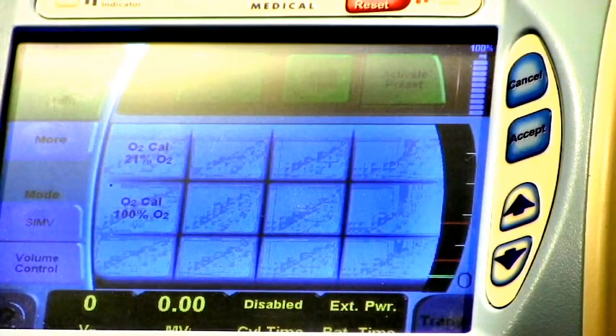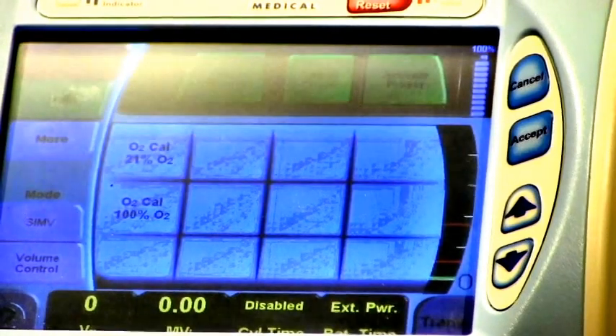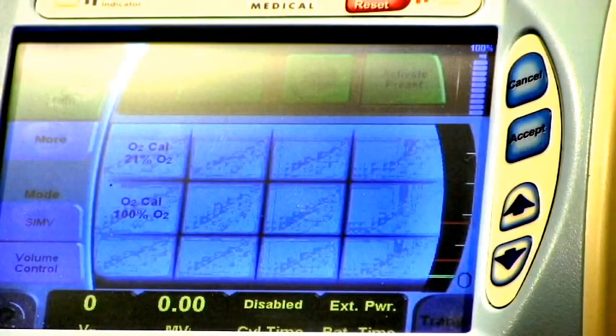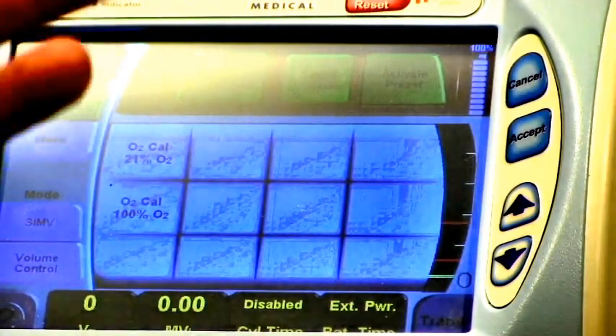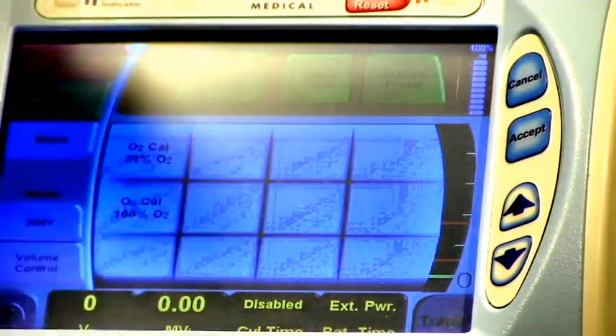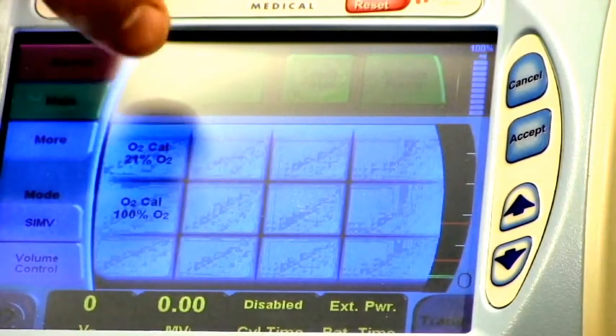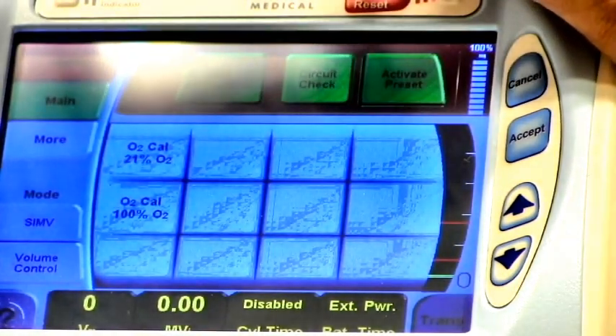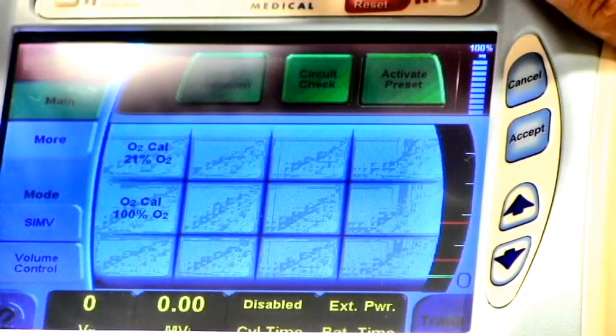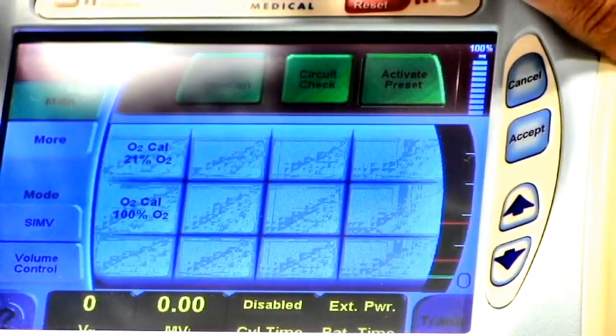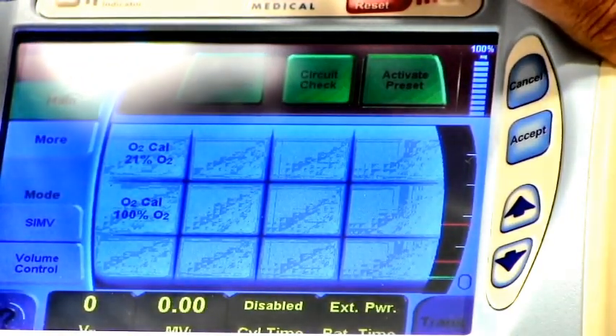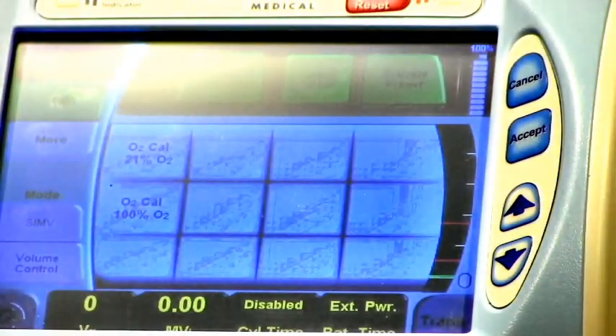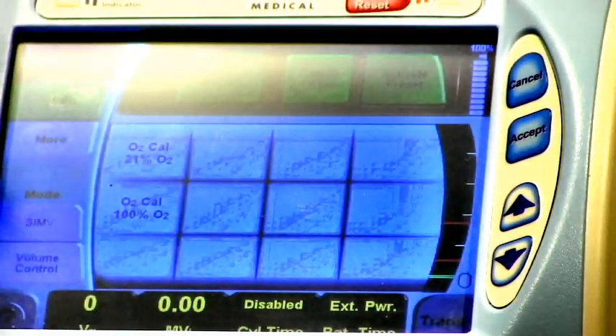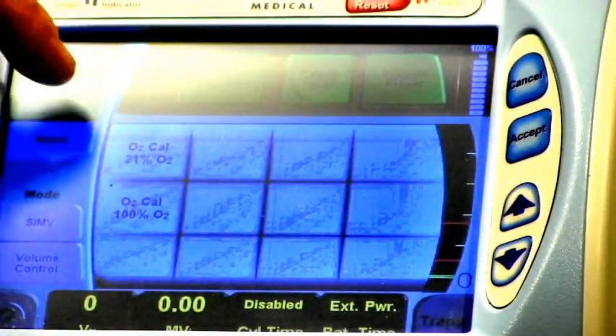You simply take your dial, move it to 100%, and then after you get that done, you're going to hit OK and accept, and that will allow you to go through it. If you do the 21% calibration, it's going to tell you to remove all your equipment on the side. So if you've taken the time to assemble it, do the 100%. If you have not assembled it on the side, then go ahead and just do the 21%. Once that's done, it will tell you accept, it's good, and then you're going to go back to the main screen.